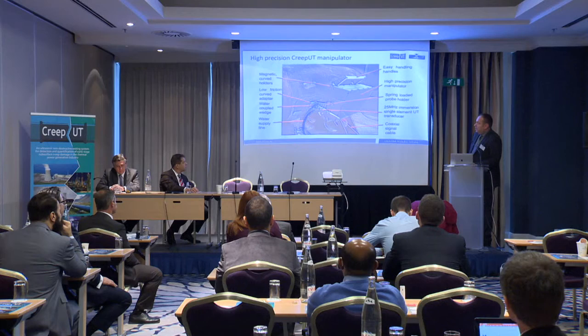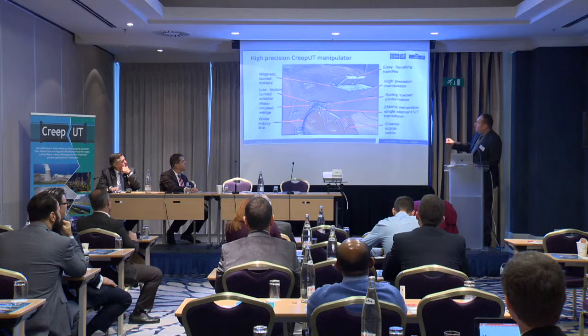This is what a high-precision manipulator looks like in action. It is attached with magnetic curved holders, and there is a low friction curved adapter with a water supply. There are easy handling handles and a spring-loaded probe holder. In this transparent plastic part, you can see a 25 megahertz probe, connected with a coaxial cable to the pulser receiver unit there. This is the pipe being tested, and this is the part close to the weld that is going to be tested, which has been prepared beforehand, polished so that high frequency ultrasound can go through the pipe.